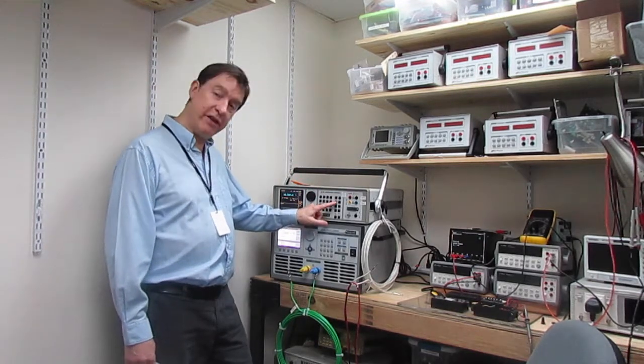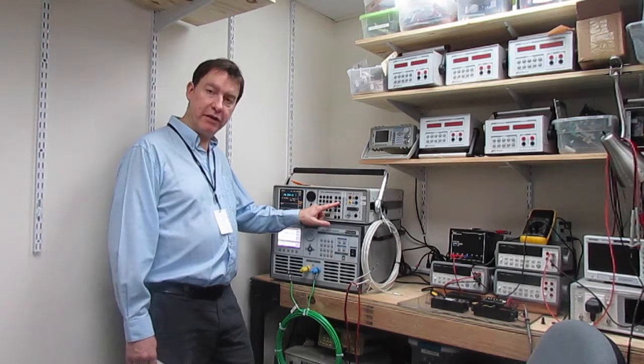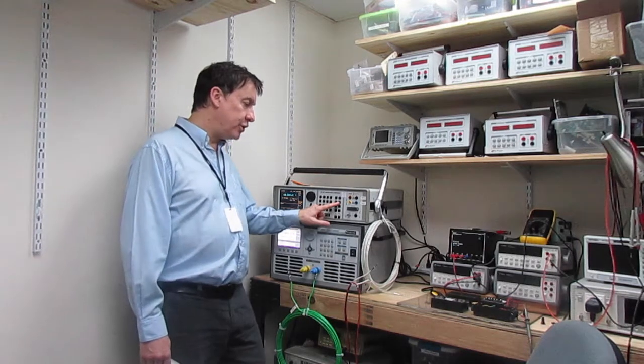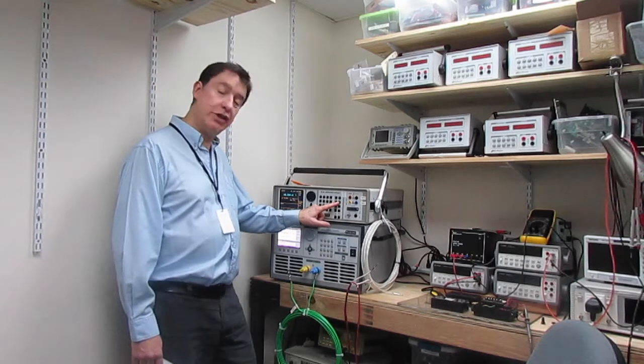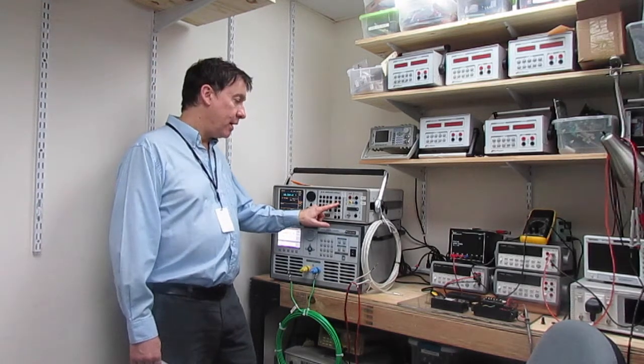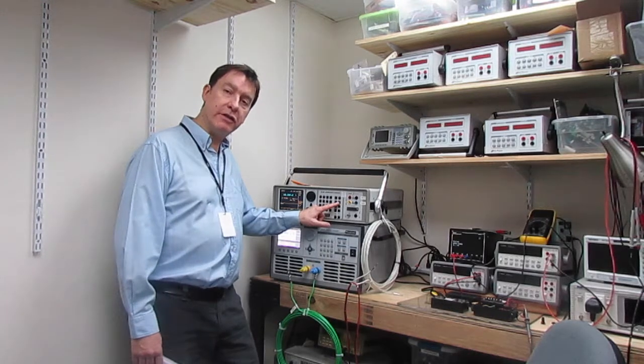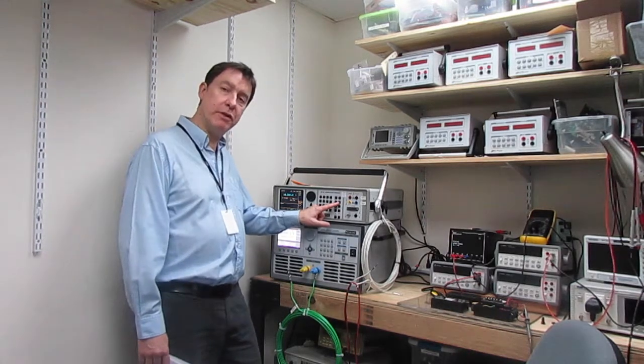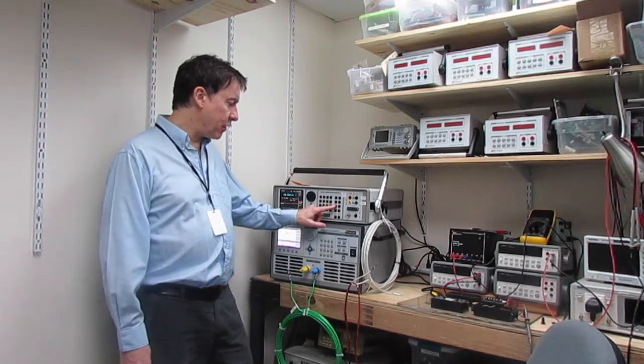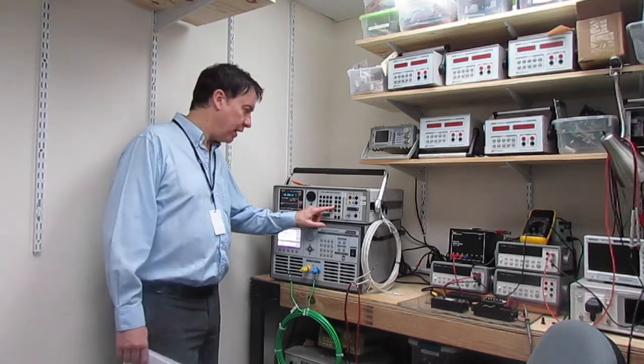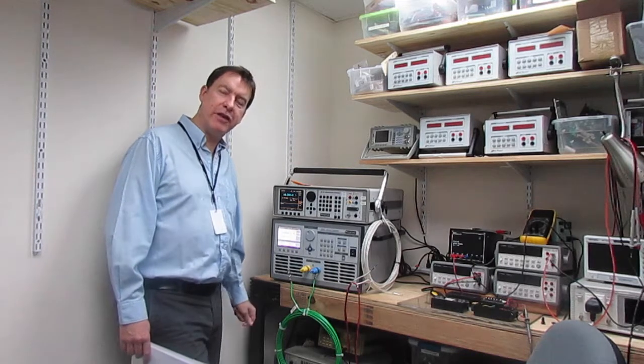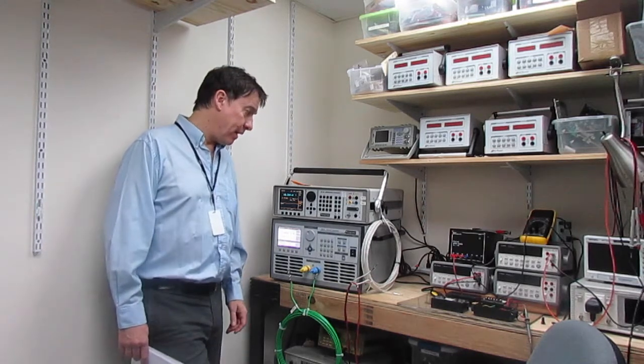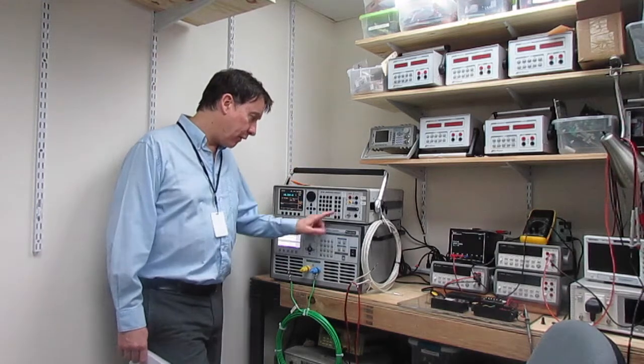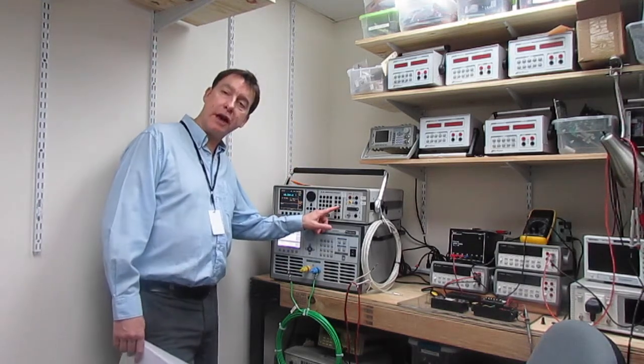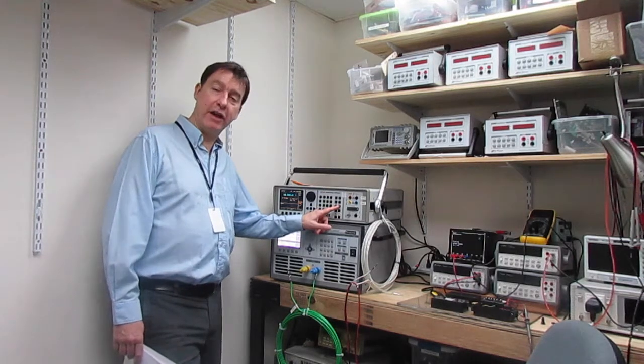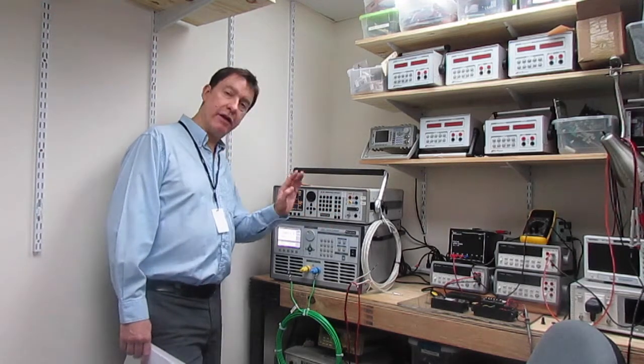Coming down, AC DC button there, and power energy button. So there we can actually look at energy in terms of watts. We can change the phase or the power factor, and this allows calibration of energy meters, electricity meters, any kind of power measurement equipment. And then coming down we've got RC, that's resistance and capacitance. Inside this calibrator it simulates precision resistors and capacitors, and again it's continuously variable. Frequency, quite useful for calibration of frequency meters. We can output a precise frequency, set it on the display, send it to the frequency meter.